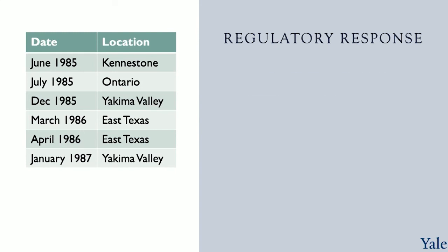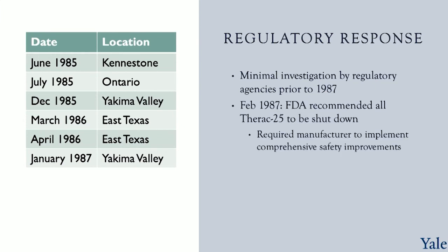For the regulatory response, minimal investigation was conducted by regulatory agencies prior to 1987, allowing the machines to continue operating. In February 1987, the FDA recommended all Therac 25 machines to be shut down and forced AECL to notify all hospitals of this. The FDA required the manufacturer to implement comprehensive safety improvements. And after five back-and-forth revisions, the Therac 25 was finally approved for safety and implementation.